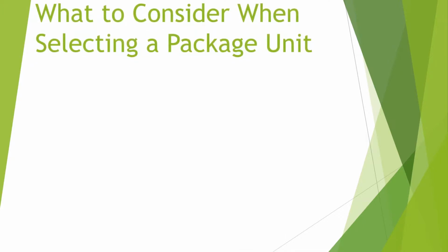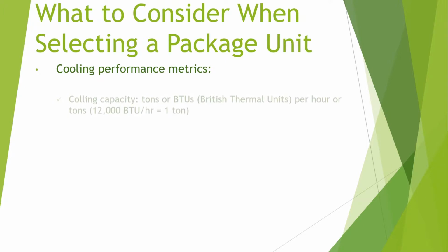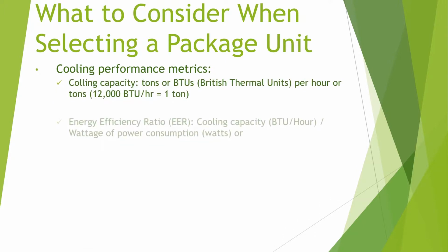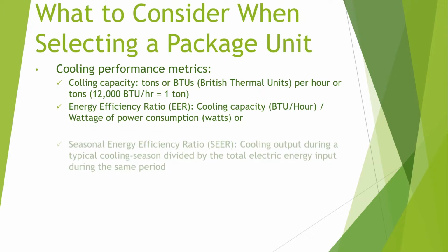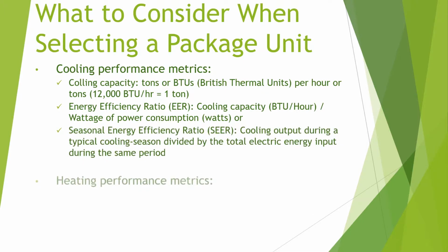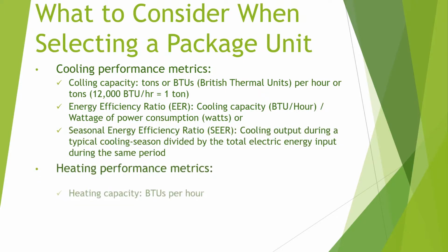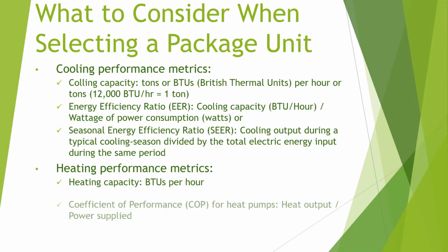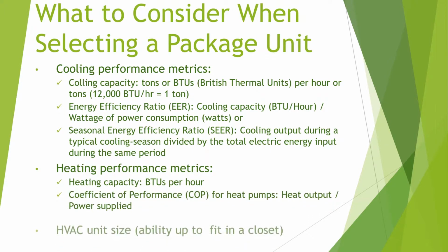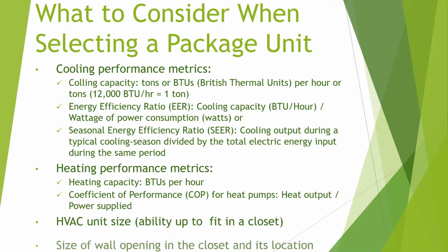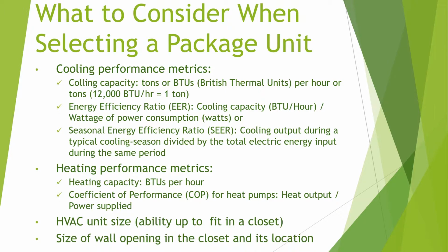When considering replacing your package HVAC unit, you should probably take into account the following aspects. One such aspect is the cooling performance metrics. One such cooling performance metric is the cooling capacity, which is measured in tons or BTUs, which are British thermal units, per hour or ton. The second such metric is energy efficiency ratio, which is measured in cooling capacity divided by the wattage of power consumption. And the third is seasonal energy efficiency ratio, which is measured by the cooling output during a typical cooling season divided by the total electric energy input during the same period.